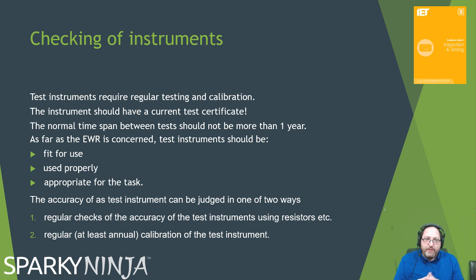Again, an annual calibration is kind of a tick box exercise. What you really should be doing is considering the dependency on every instrument and deciding if that's enough. If you only get it out now and then, it would most likely be okay, but I'd always self-check it before I used it on something that I know a value of, as a self-checking activity.